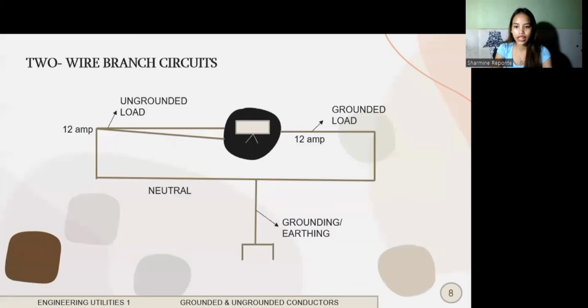I have here the illustration of the two-wire branch circuit. Same lang ni sila sa example that I presented in the single wire circuit. Ang pinagkaiba lang is we have two wires for the ungrounded load. We have 12 ampere here. This 12 ampere will be divided in two. So each wire will carry the same or even load of electricity. These two wires will flow to the appliances, then to the grounded load. It will either go back to the source using the neutral conductor or back to the ground using the grounding process.